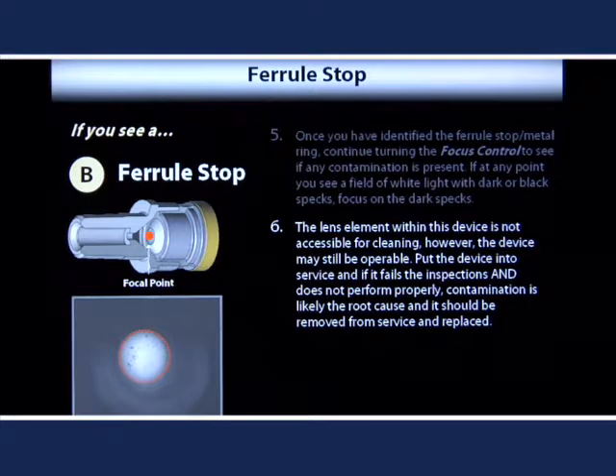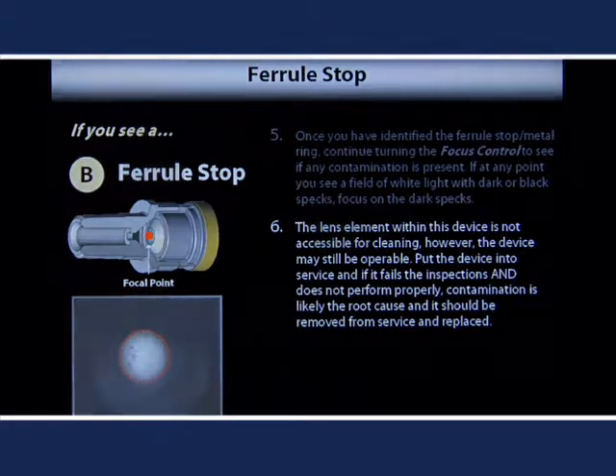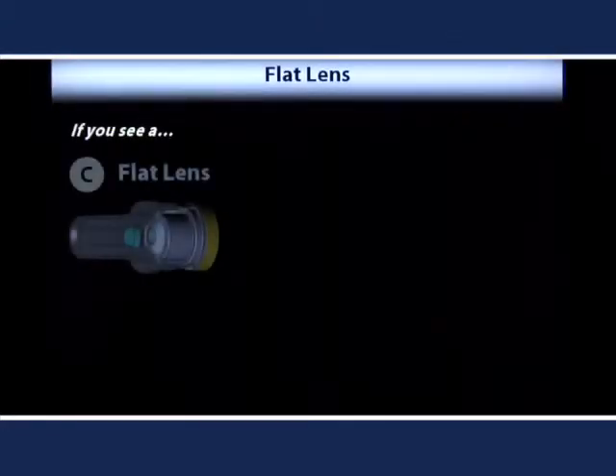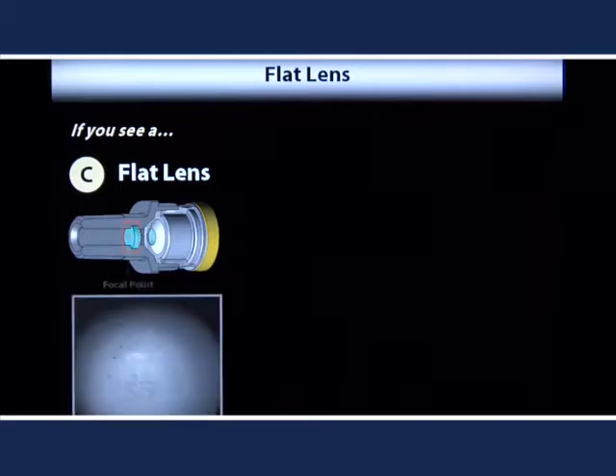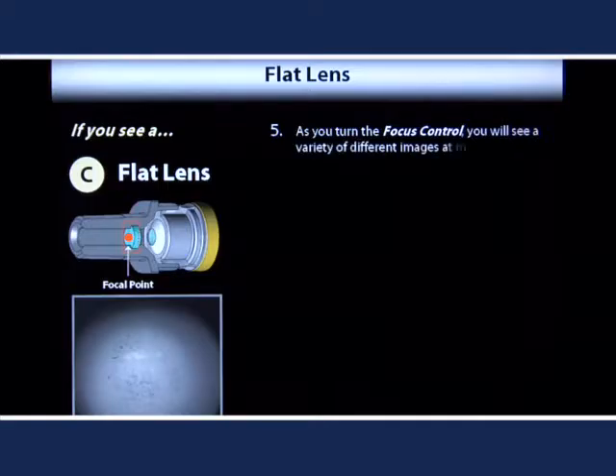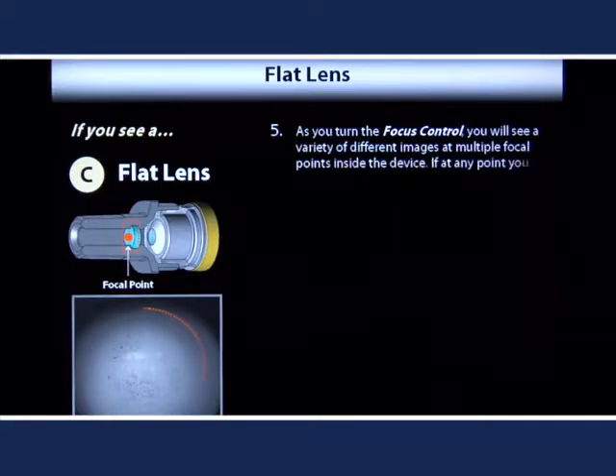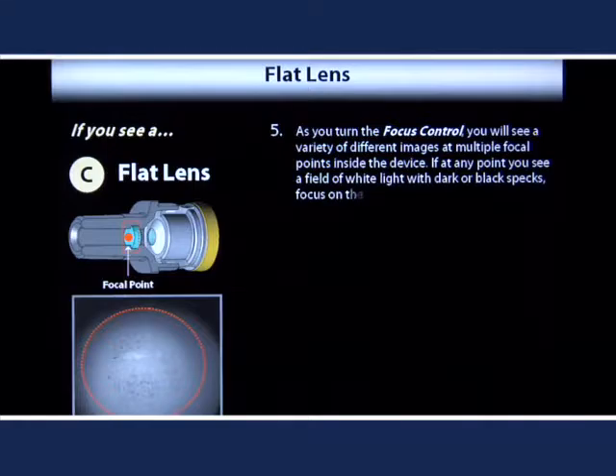If it fails the inspections and does not perform properly, contamination is likely the root cause, and it should be removed from service and replaced. If there is no discernible fiber image or metal ring, then it is most likely a flat lens design. As you turn the focus control, you will see a variety of images at multiple focal points inside the device. If you see a field of white light with dark specks, it is likely the surface of the flat lens.